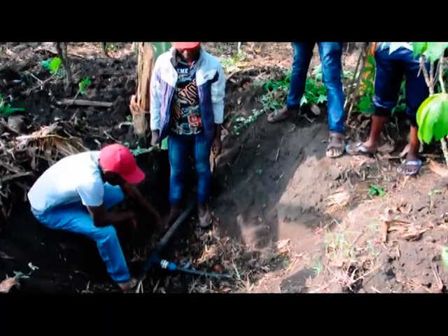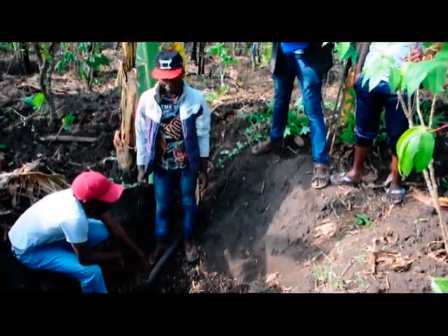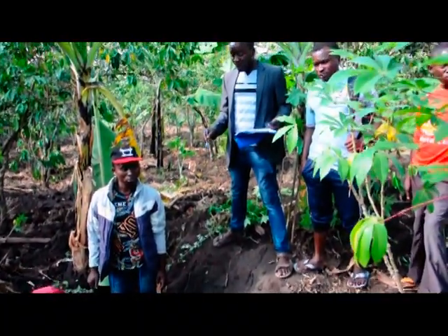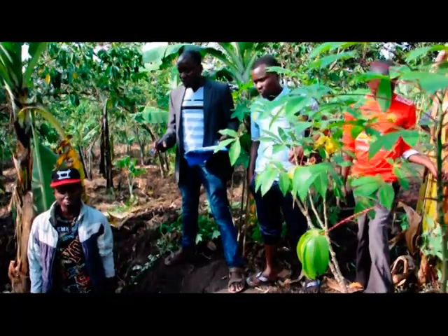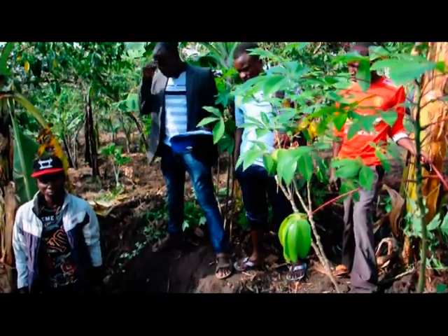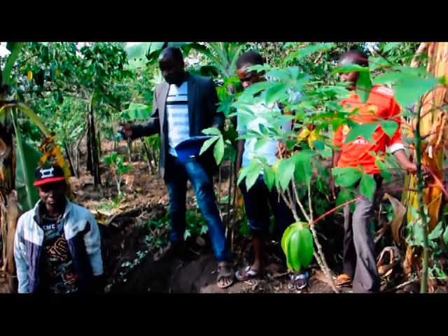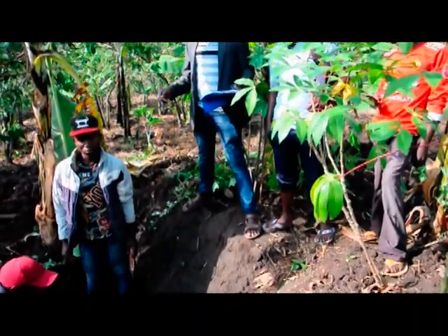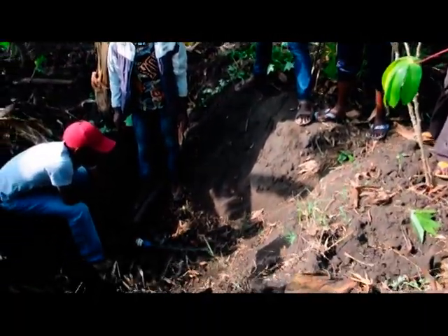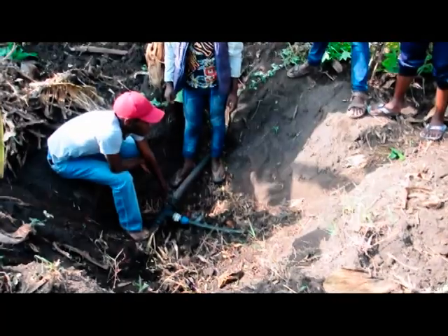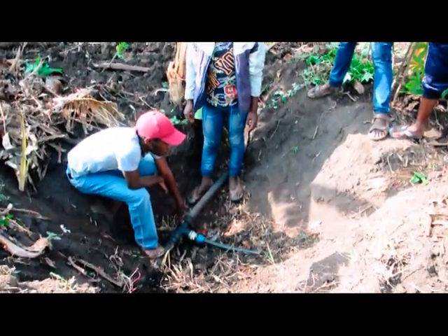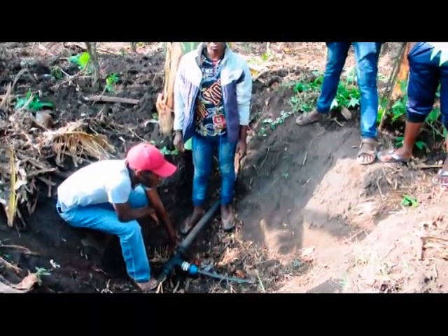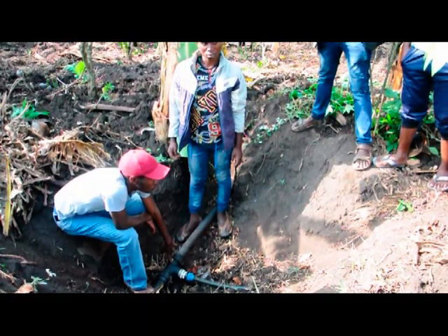And here now, the main line from Kabole has been reduced from a 90mm pipe to a 63mm pipe. The strategy here is also that we need to put up a manhole. There was a manhole, but we removed it when we were doing rehabilitation of the system, when we came in as the company. So the next step is to make sure we put a manhole. Maybe we also need a control valve. This can also help us to gauge the water that we can take to Kalonkoire Trading Center and then to other taps that are all on this main line from the Kabole main tank.